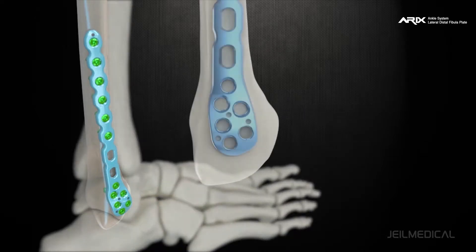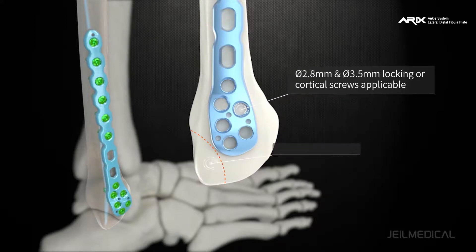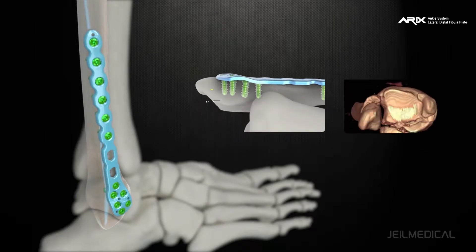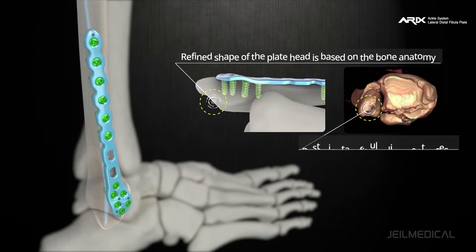The distal part of the plate is designed to be thinner than 1.3 millimeters, minimizing friction with surrounding tissues. The ARIX fibula plate is also designed to prevent screw penetration through the recess for the PTF ligament, thereby preventing ligament damage.